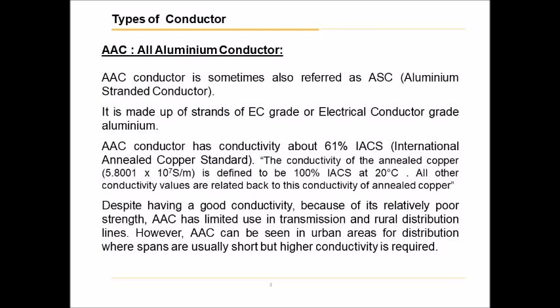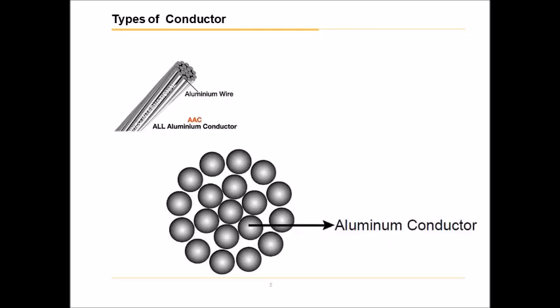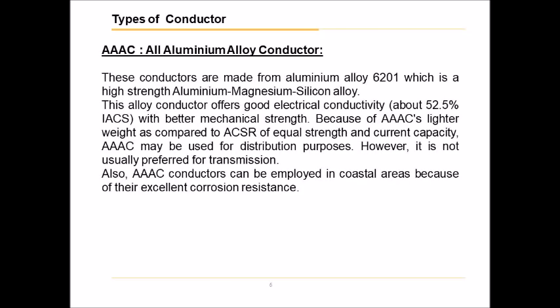Despite having good conductivity, because of its relatively poor strength, AAC has limited use in transmission and rural distribution lines. However, AAC can be seen in urban areas for distribution where spans are usually short but higher conductivity is required. The picture shows an example of AAC conductor.